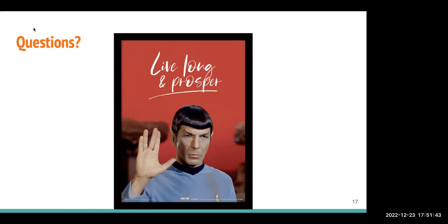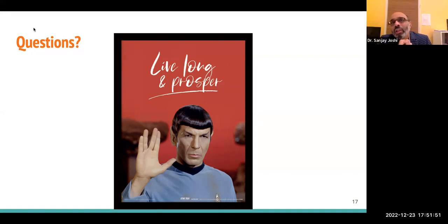Okay, sir. And also, I wanted to ask, if there is exposure to radiation, are there any standards for that? Yes, absolutely. Exposure to radiation, if it's X-rays, there is a 60601 sub-standard for X-rays. For MRI, there is another standard.